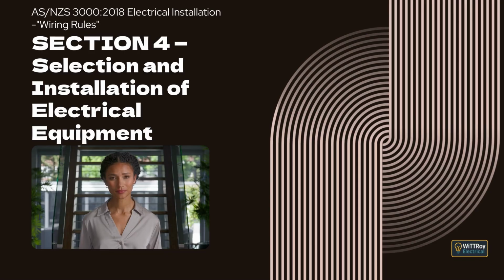This clause explains that socket outlets must be installed so they are not exposed to undue mechanical stress or damage during normal use. It explains that where socket outlets are installed in floors or horizontal surfaces, they must be arranged to prevent the buildup of dust or water. It explains that where socket outlets are installed close to a floor, they must be positioned so plugs are withdrawn horizontally, unless certain protective design conditions are met.